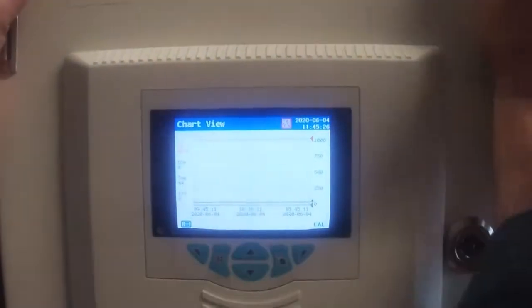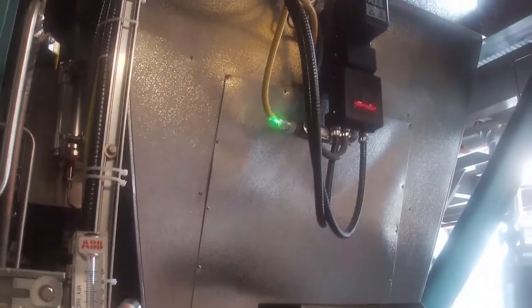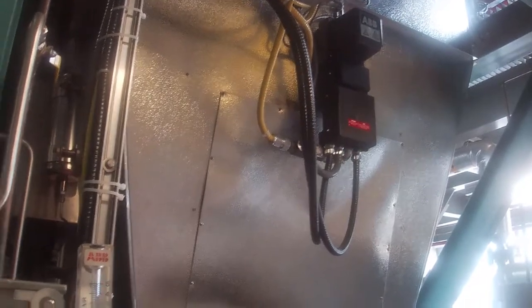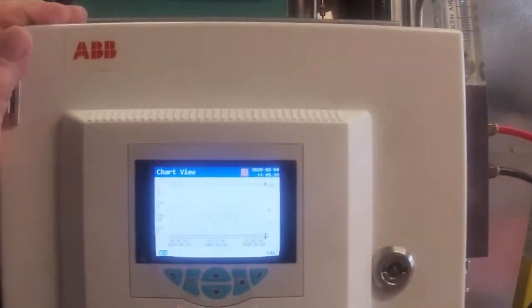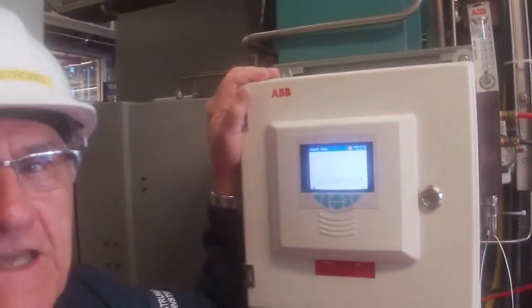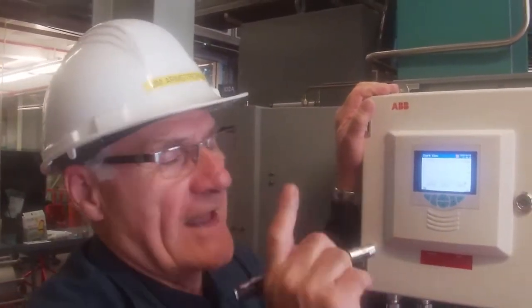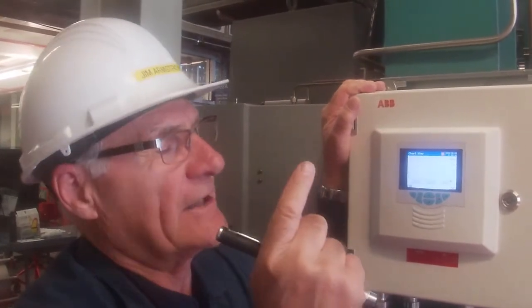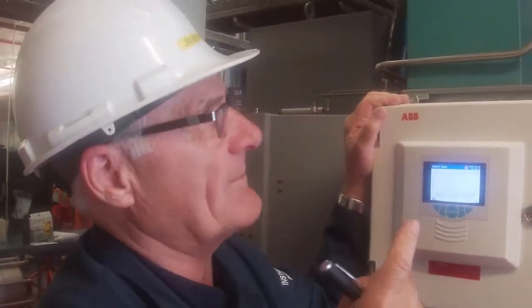To do that, up on the sensor itself, right here, you will see two cables coming in which are yellow in color. Those are thermocouples, and they're type K thermocouples, which is identified by the yellow wire itself. And they're looking at the temperature in the exhaust gas stack, and we're also looking at the temperature of the inlet air. And so therefore they're able to calculate what the temperature differential is across there and calculate combustion efficiency. You can look those up on tables if you wanted to. This guy will actually calculate it for you, and it puts it onto the boiler display itself for us.